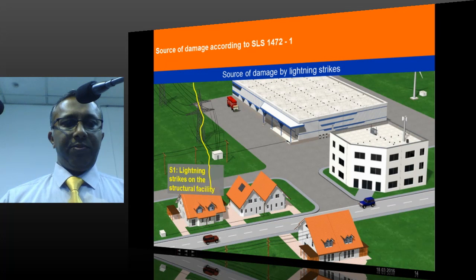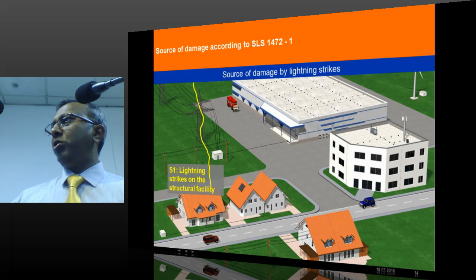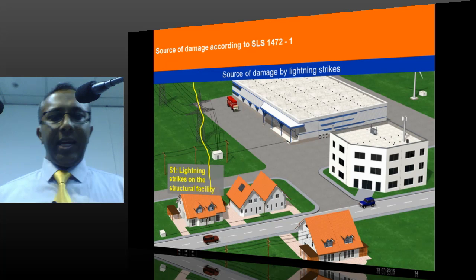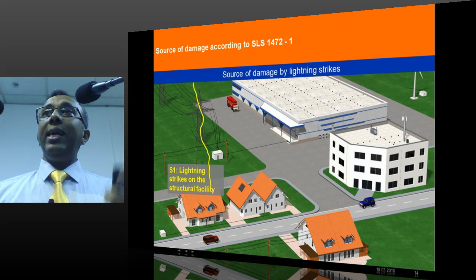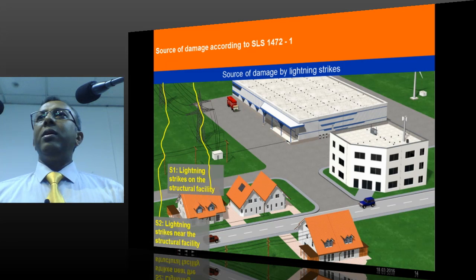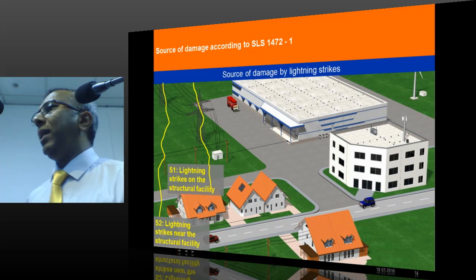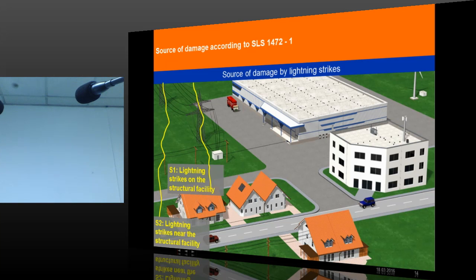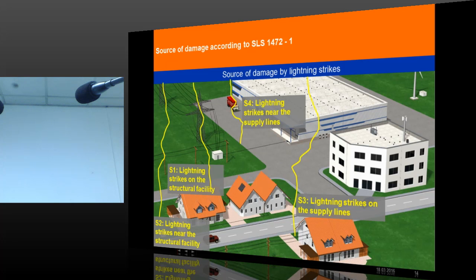Source of damage. What are the sources of lightning which can damage or which can create problems for the building? S1, source 1, is a direct lightning strike on the building. Source 2 is a lightning strike very close to the building, because in case of a lightning strike very close to the building, due to the potential rise, all electrical apparatus which is connected to ground will experience a high potential and there will be flashover. S3 is a direct lightning strike on the service, and S4 is a lightning strike which is near to the service. These are the four kinds of lightning strikes which can create trouble for us, which can create failures.